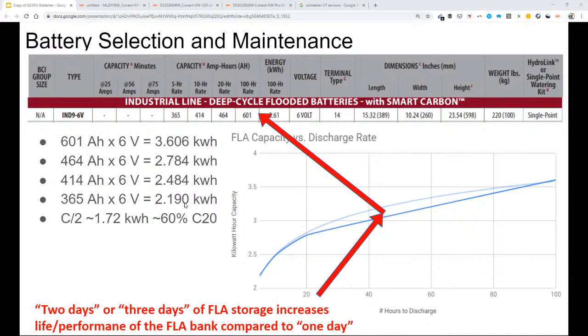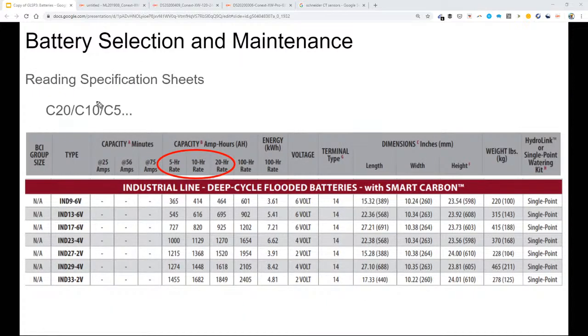And there's a point of no return where, if you notice on this sheet, they're not giving you a 2-hour discharge capacity. They're giving you a 100-hour discharge capacity. You can see the energy. The battery's even more efficient at a 100-hour discharge rate than a 20-hour discharge rate. So it's these off-grid customers on giant lead acid battery banks that have 3 days or more, 4 days or more storage, that are having really good experiences with their lead acid batteries. If you have less than 3 days, less than 4 days worth of storage, you're not going to have the same experience. The closer you get to this 5-hour discharge rate, the more inefficient your system becomes.